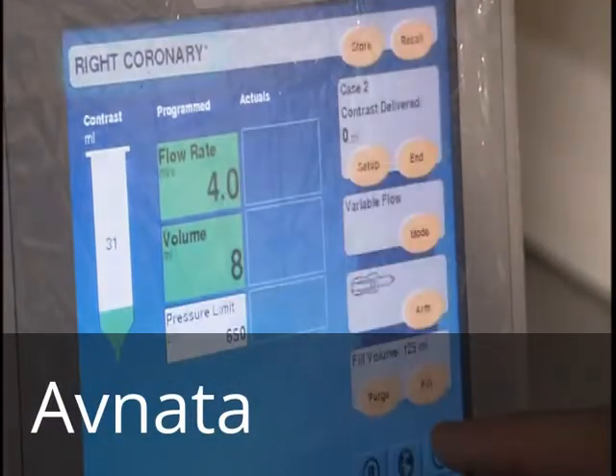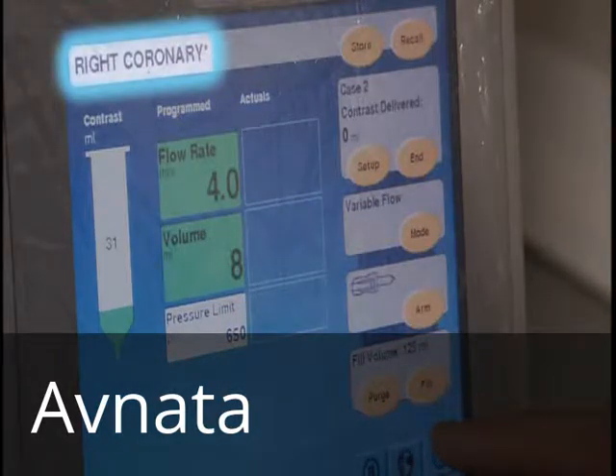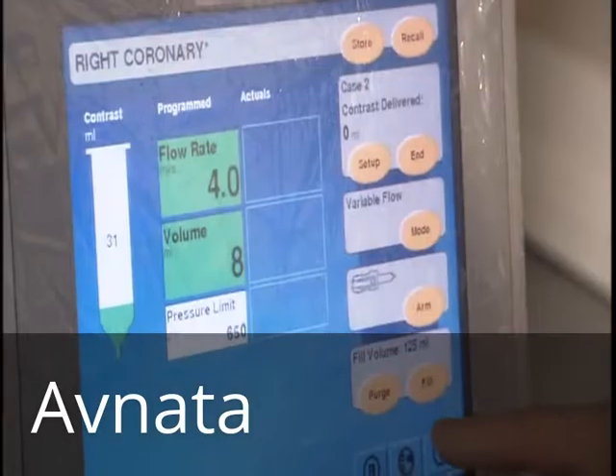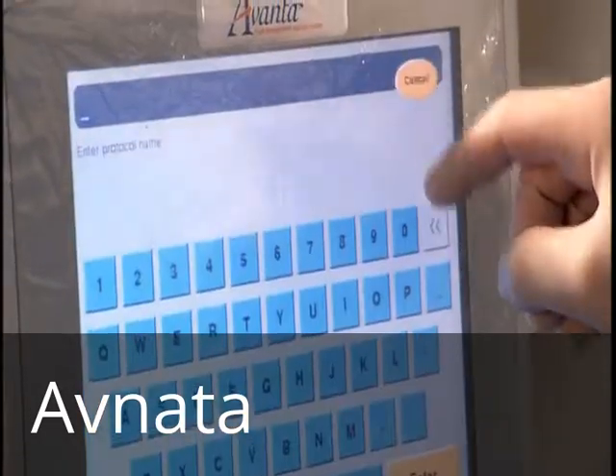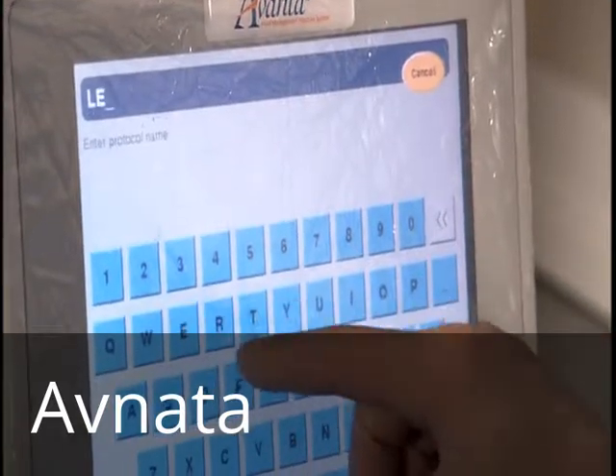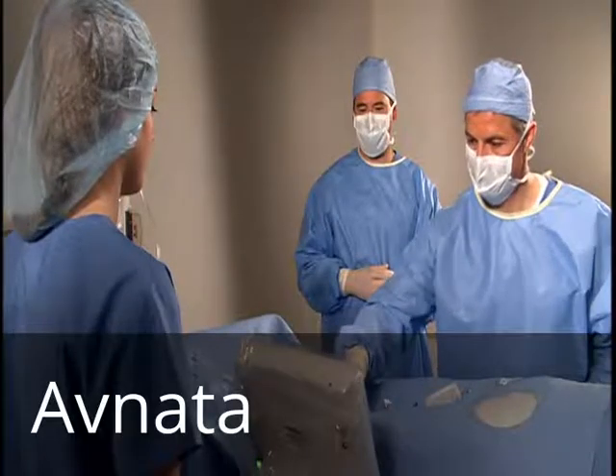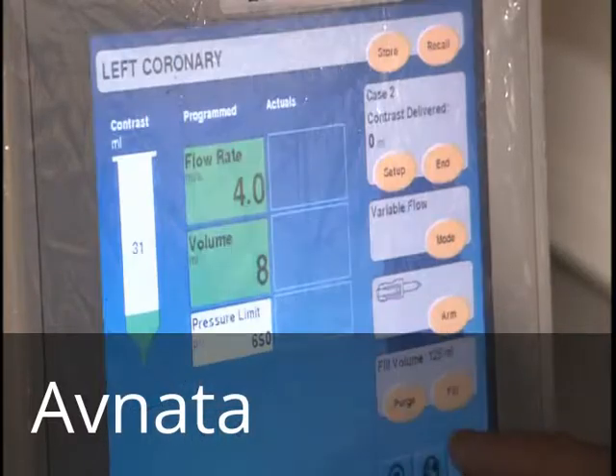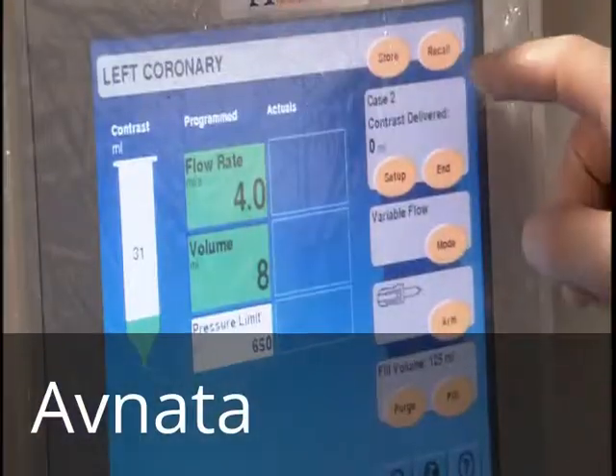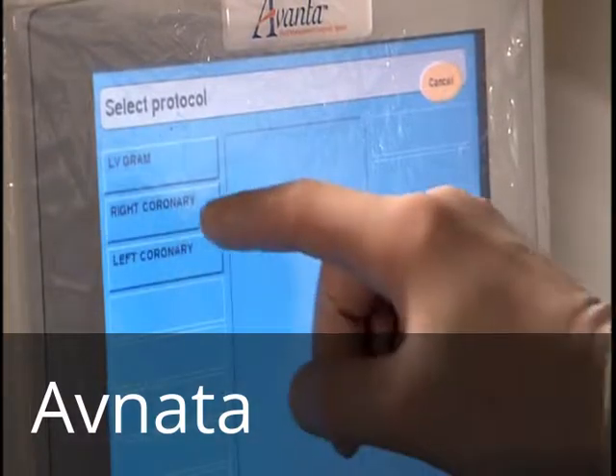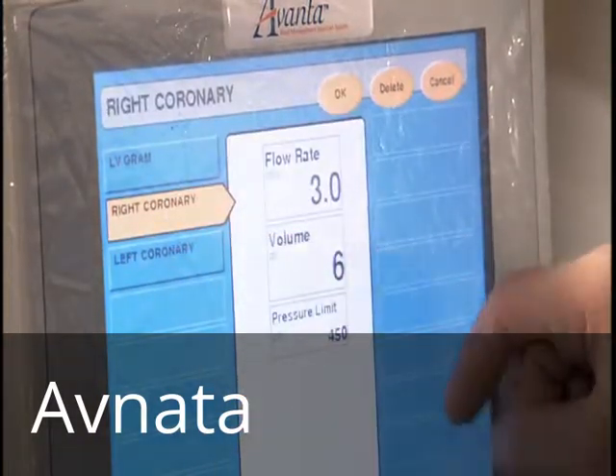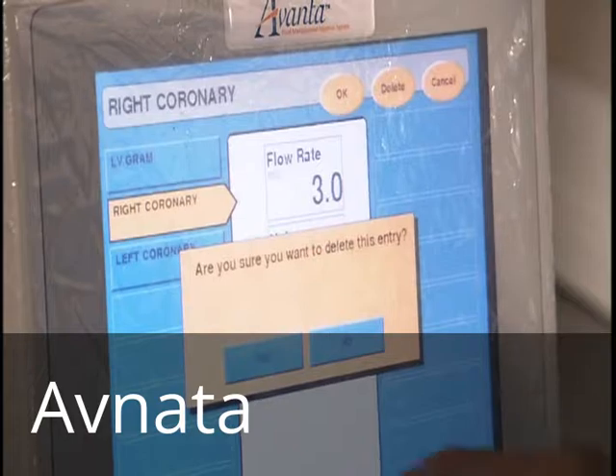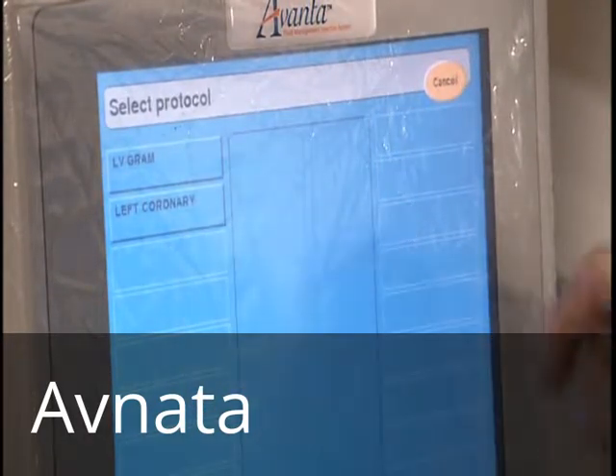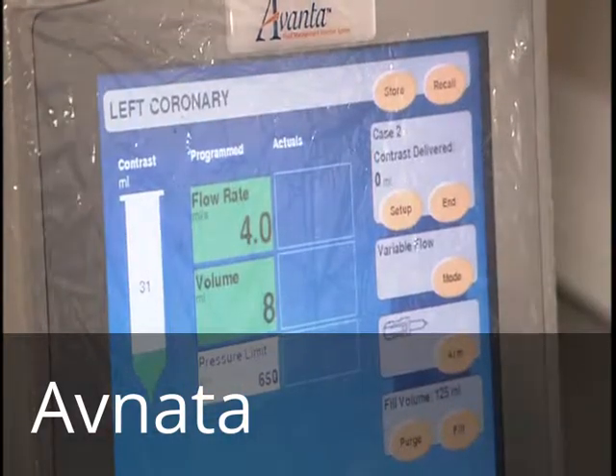If a protocol is recalled and changed on the main screen, an asterisk appears after the protocol name, indicating that it is no longer the stored protocol. To save the changed protocol, touch Store, type a new title, then touch Enter. The new protocol will be saved, as will the original protocol. To delete a protocol, touch Recall and select the desired protocol. Touch Delete and respond to the prompt. Touch Cancel to return to the main protocol screen.